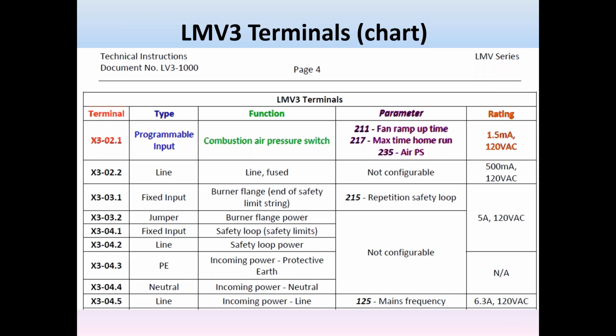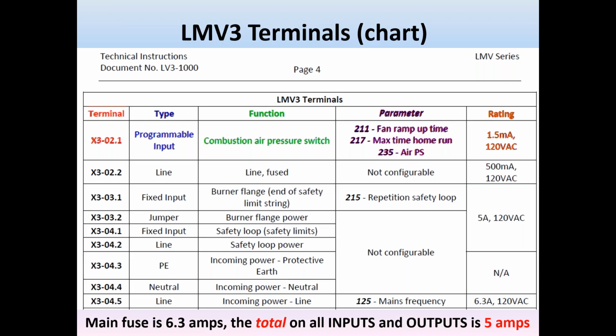Finally, on the right, we show a rating of 1.5 milliamp is the input. The air pressure switch is a very light load. It's 120 volts. And then you see the various amp ratings of all the terminals. Keep in mind that the main fuse is 6.3 amps. So the total on all of the inputs and outputs is a maximum of 5 amps. And then about 1.5 amps is left to run the LMV3 itself, which would be the servos and the load controls. So 5 amp total on all the inputs and outputs, but each individual terminal is rated higher than that.